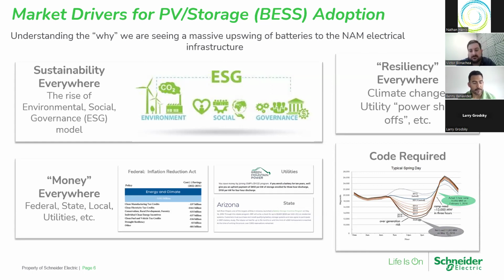And a lot of that's funded through the federal government. So we're seeing a huge uptick in funds, particularly for schools, military sites, and federally funded businesses, where a lot of this money is being invested. So that's a huge avenue and segment for microgrid and battery energy storage growth and resiliency, right? The need to have backup power available. One way to do that traditionally has been through a genset, but through an energy storage system you can also enable resiliency. Now, to Victor's point, a lot of these energy storage systems serve as loads, but if you design the system properly with adequate isolation, that energy storage system can provide backup power. We'll talk about that in the later slides. And then, of course, there's the code requirement in the 2023 National Electric Code that energy storage systems can be used as a standby source.